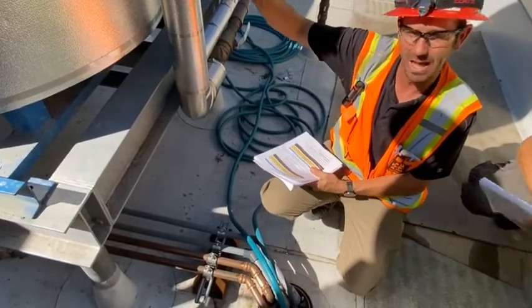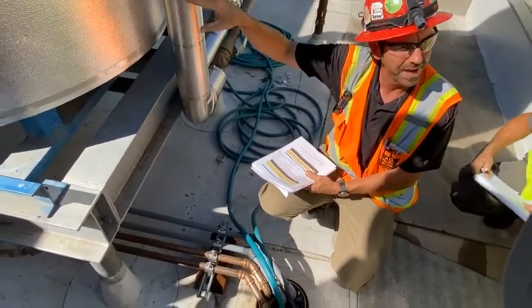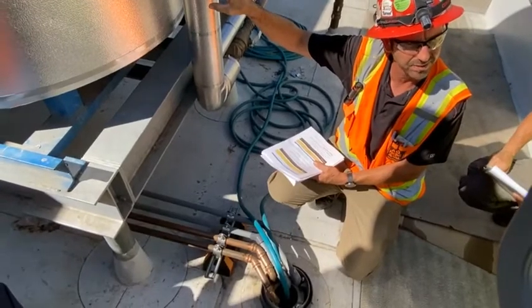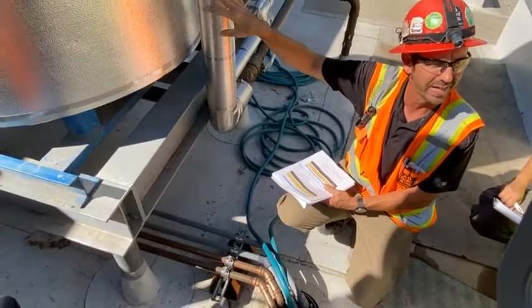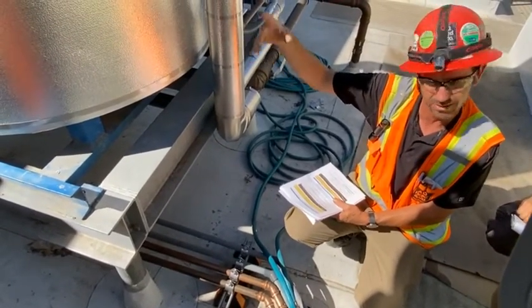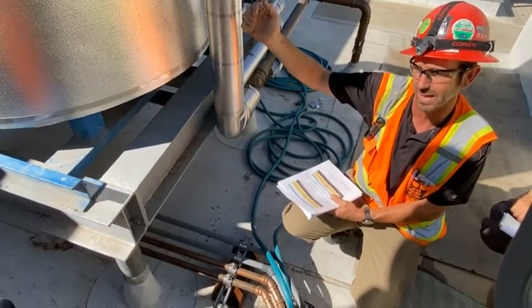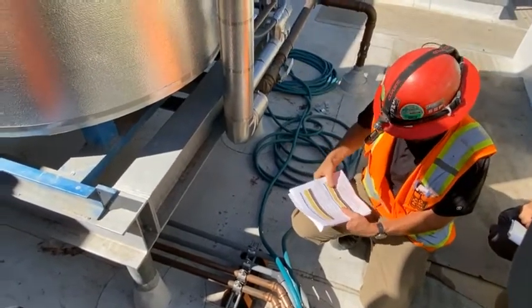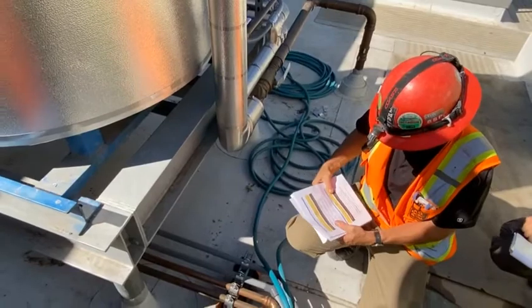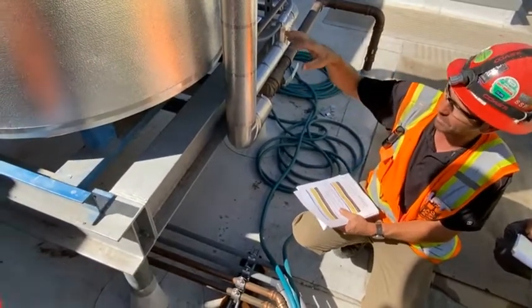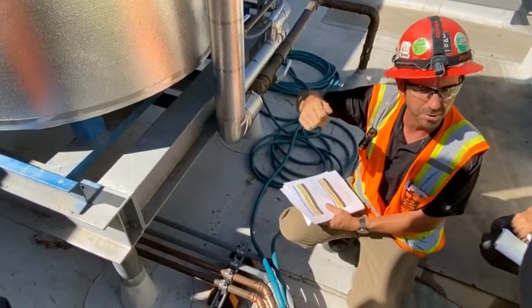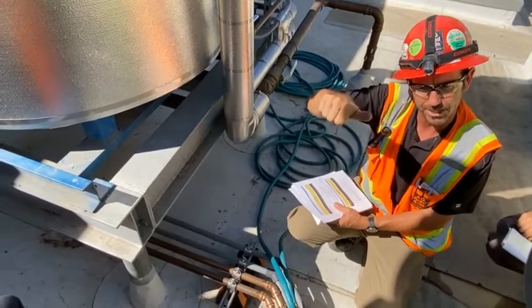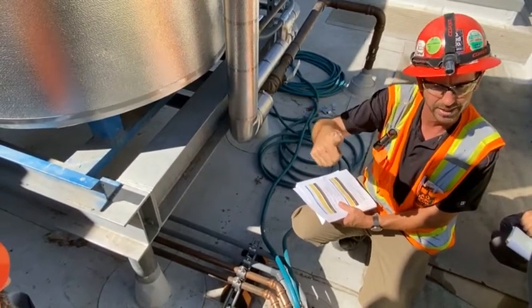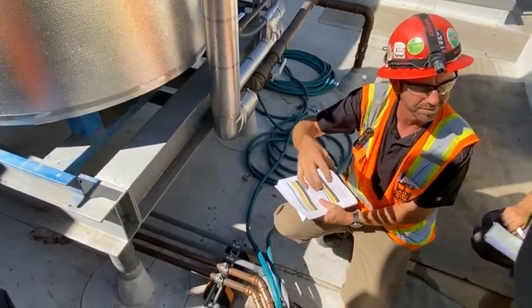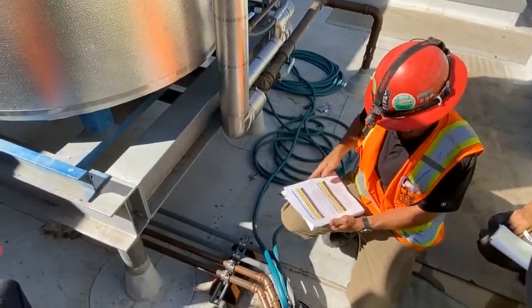This is a cement-lined tank, so the manufacturer does not require anode rods for the tank, so you don't need to worry about doing anything of that. It is an optional device that you can install down the road if you deem it necessary, okay? And if the tank is fitted with a pressure relief, they want you to monthly gently lift the pressure relief and then gently let it come back down and seat itself as a monthly inspection.